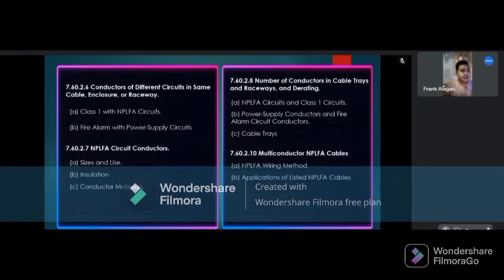So next is Article 7.6.2.6, conductors of different circuits in the same cable, enclosure or raceway. Class 1 with NPLFA circuits, or non-power limited fire alarm circuits, shall be permitted to occupy the same cable, enclosure or raceway without regard to whether the individual circuits are alternating current or direct current, provided all conductors are insulated for the maximum voltage of any conductor in the enclosure or raceway.